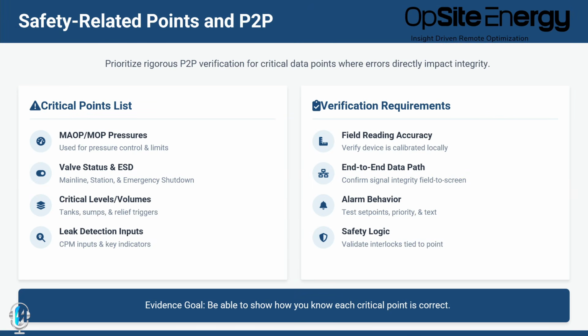Aside from just focusing on the usual suspects for critical points, you really want verification requirements in place: the field reading is accurate, the end-to-end data path looks good, there's good alarm behavior, and there's good safety logic - so if something has to fail open or fail closed, you're checking that box. In terms of safety logic, something latches properly, and you want to make sure you've got a good latch there.